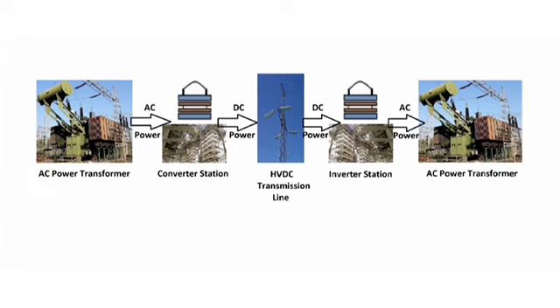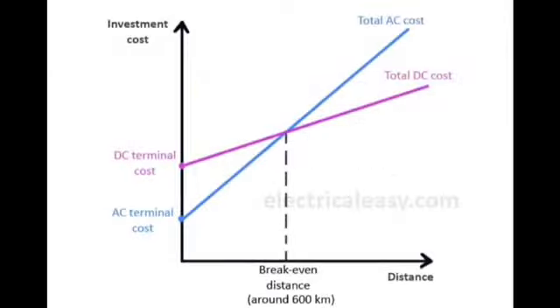These converter and inverter stations increase the capital cost of an HVDC power system as compared to the capital cost of an HVAC power system. As shown in the graph, up to the break-even point, around 600 kilometers, the cost of HVDC transmission is higher than that of HVAC transmission, whereas after 600 kilometers, the cost of HVAC transmission is higher than that of HVDC transmission. Hence, for transmission beyond 600 kilometers, the HVDC transmission system is economical as compared to the HVAC transmission system.